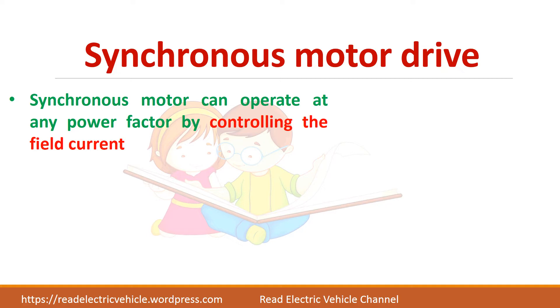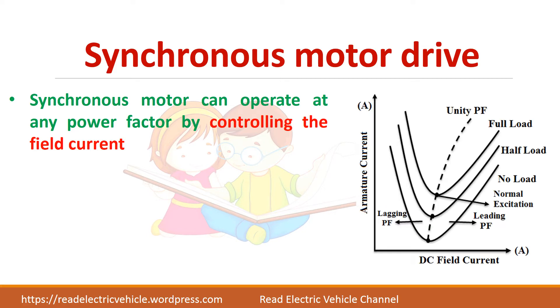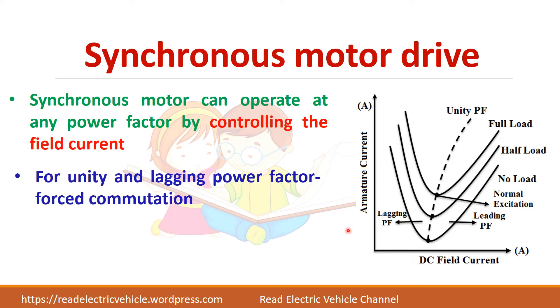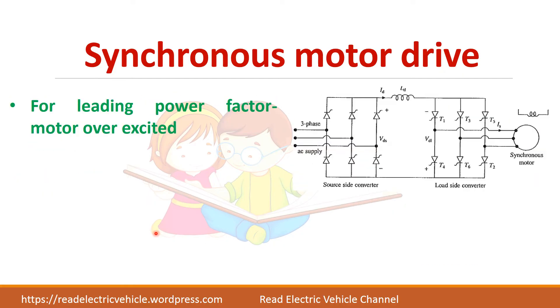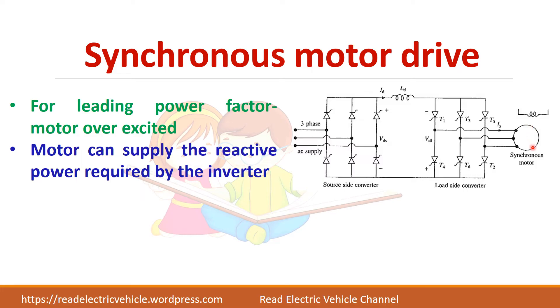The synchronous motor drive can operate at any power factor by controlling the field current. It can operate at lagging power factor, leading power factor, or at unity power factor. For unity and lagging power factor, the thyristors in the load-side converter are force commutated, meaning we need an external circuit to commutate the thyristors. For leading power factor, the motor is normally overexcited, so machine voltages can be used to turn off the thyristors — that is, load commutation is possible. In such cases, the motor can supply the reactive power required by the inverter.